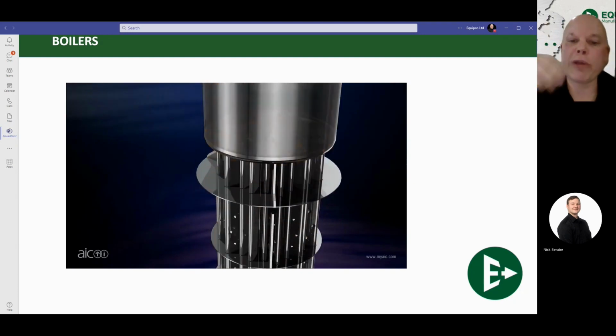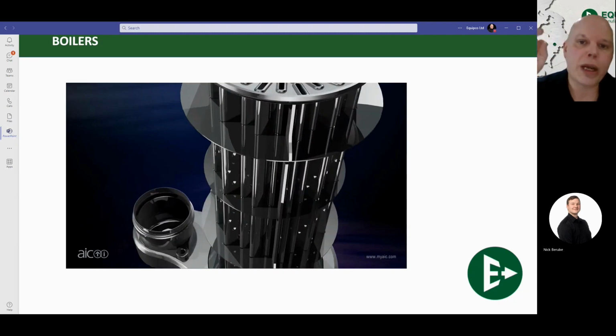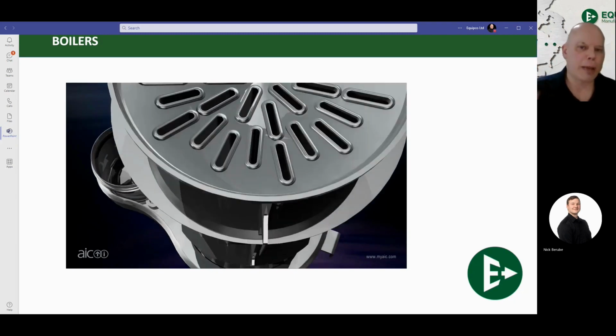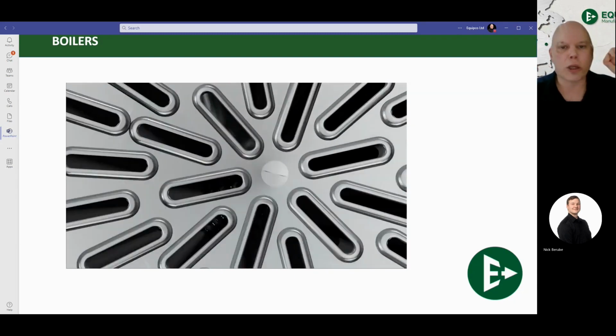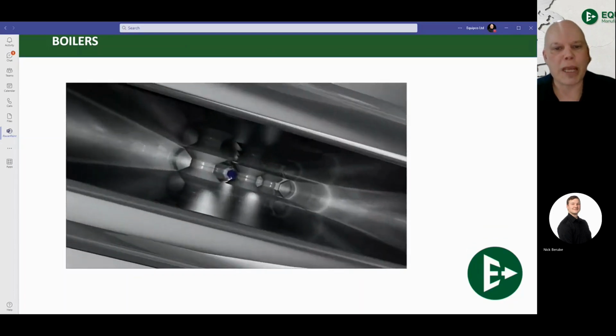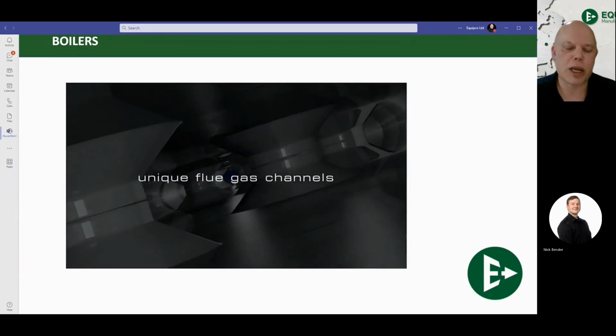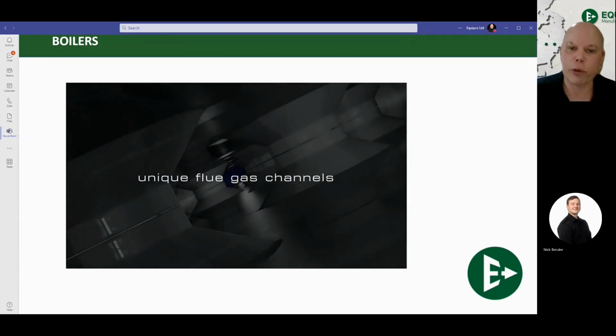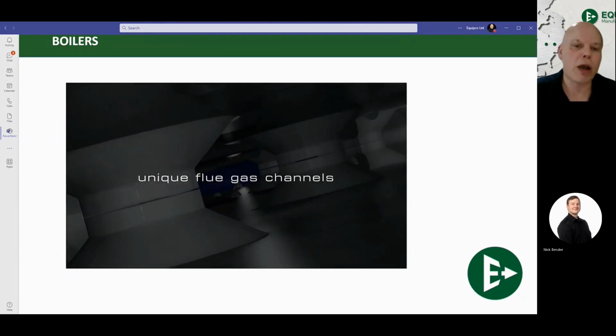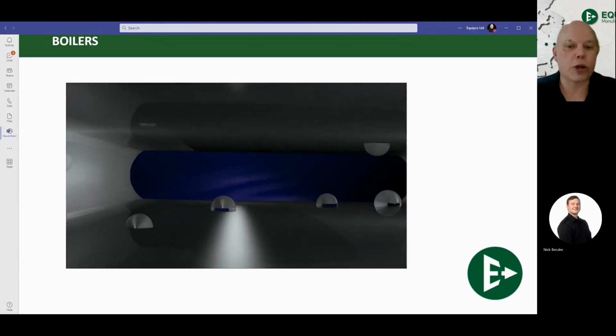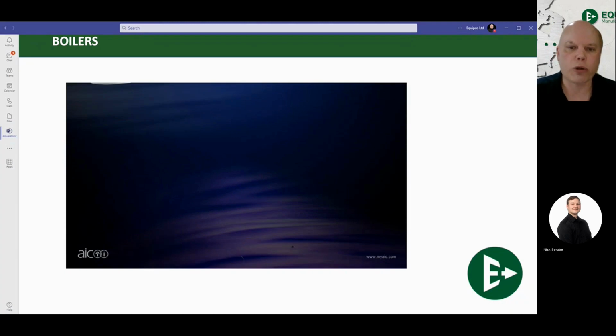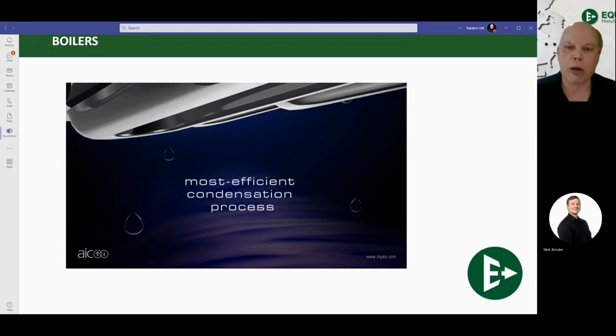Now, here we're going to be flame. We're going to go right down this fire tube. So I'm now flame, and I'm going to turn into the flue gas. I'm going to go right down this fire tube. I'm going to be interrupted by these little nodules on the side to slow down that flue gas moving through. As I slow down, I'm stripping all my heat away and I start to condense. There are my little water droplets. The condensation comes out of the bottom.